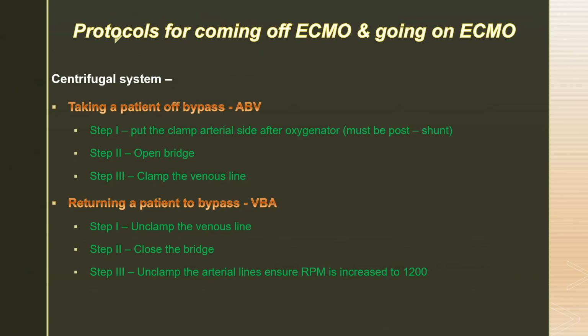But it is exactly opposite for the roller pump. If by chance you are using a roller pump, never put the clamp on the return line of the roller pump when the roller pump is moving, otherwise it can cause a rupture of the tube.